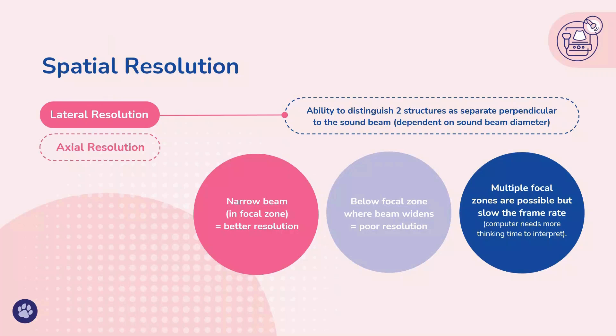Lateral resolution is our ability to distinguish two structures as separate, perpendicular to the sound beam, and this is dependent on sound beam diameter. Although we are looking at a two-dimensional image on our screen, the sound wave beam entering the animal has a thickness to it — it's not completely flat. At any given level the machine is making an average of what happens at that depth. If the beam is particularly wide we're getting an average of a lot of things and it's very inaccurate; if it's really narrow we get very good accuracy and resolution. The focal zone is the part of the sound beam with the narrowest diameter and therefore the best lateral resolution.